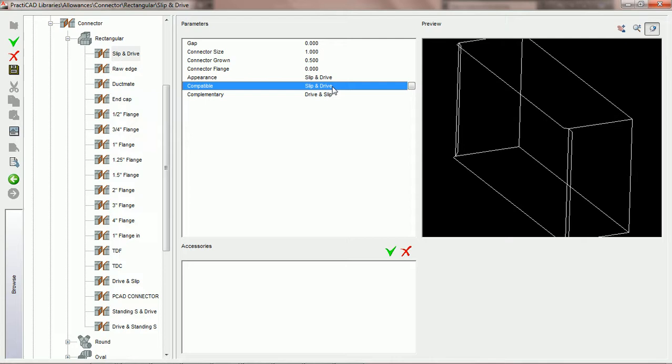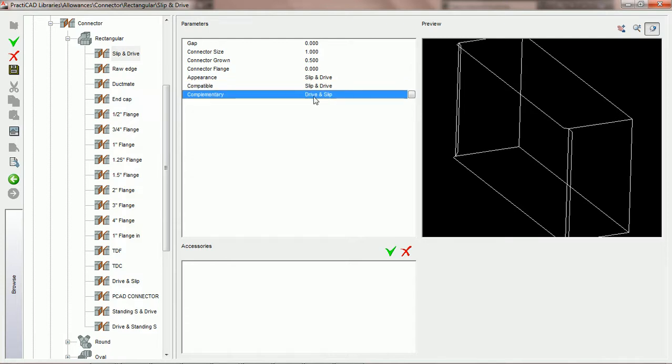However, if we were to take the second fitting we place in a drawing and rotate it 90 degrees, now we'd actually be attaching the depth of that fitting to the width of the first fitting. In that particular case, we need the connectors on the second fitting to change. And that change is defined by whatever connector you've chosen in your complementary selection set. So what we're going to do here is say for slip and drive, we would like to make a complementary connector of drive and slip.